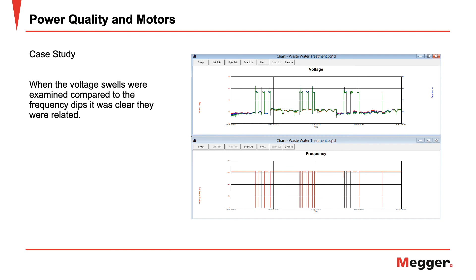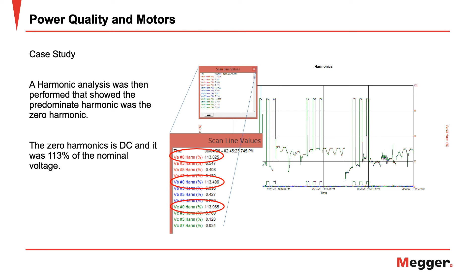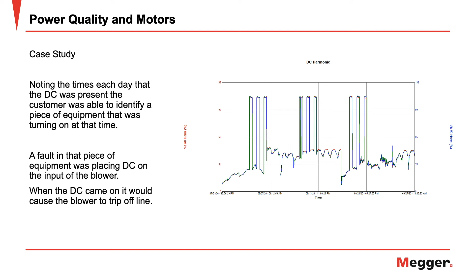We then performed a harmonic analysis, and it showed that the predominant harmonic was the zero harmonic. The zero harmonic is DC, and it was 113% of the fundamental voltage. Noting the times each day that the DC was present, the customer was able to identify a piece of equipment that was turning on at that time. A fault in that piece of equipment was placing DC on the input of the blower. So when the DC came on, it would cause the blower to trip offline.